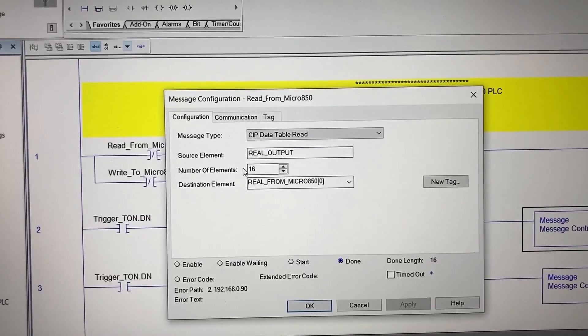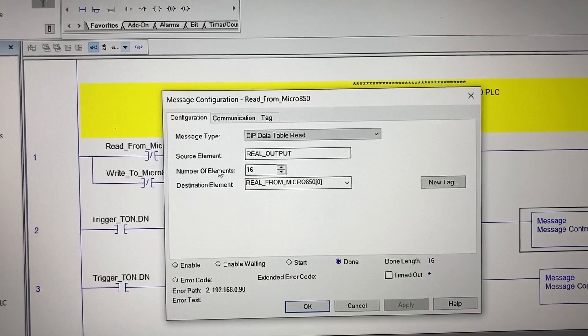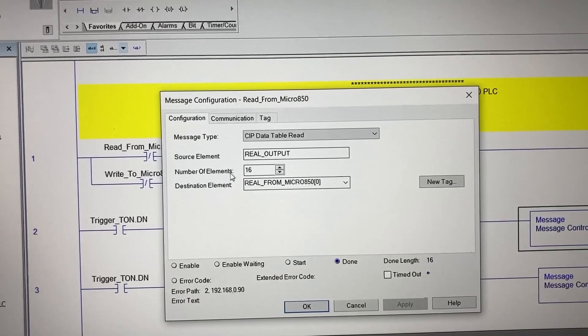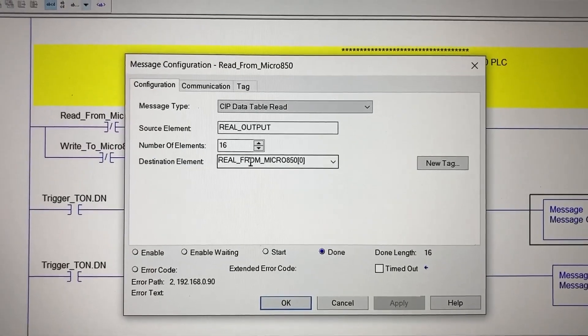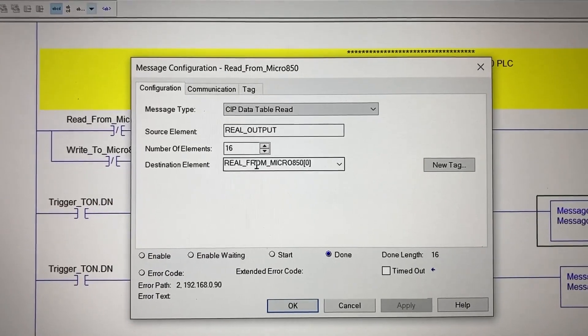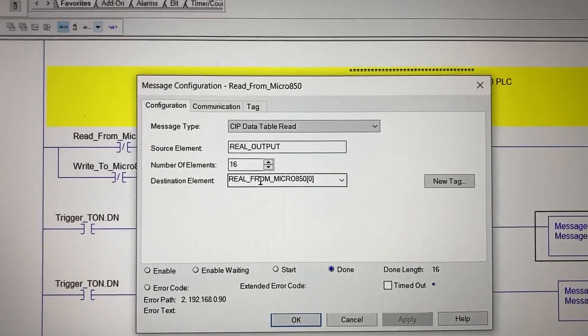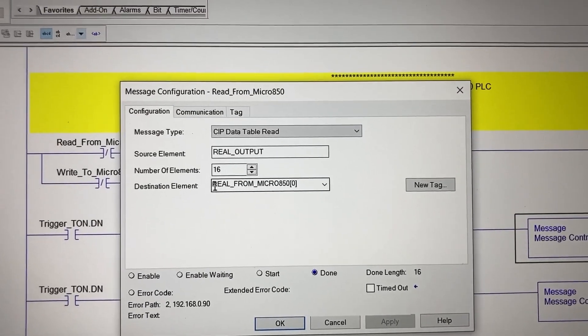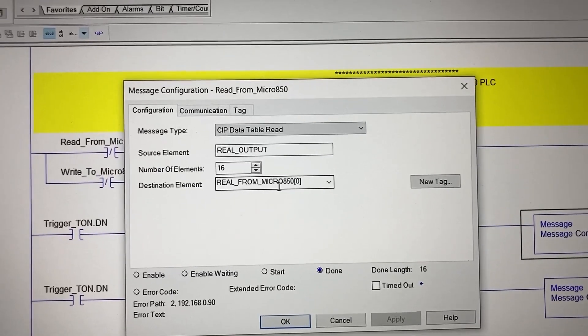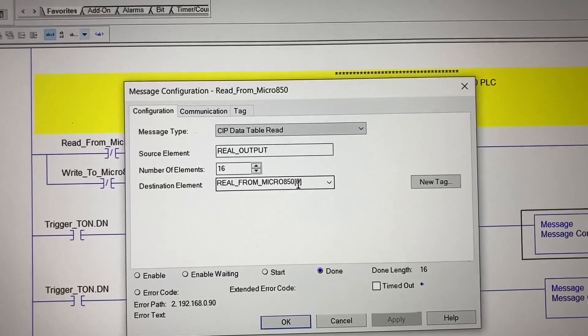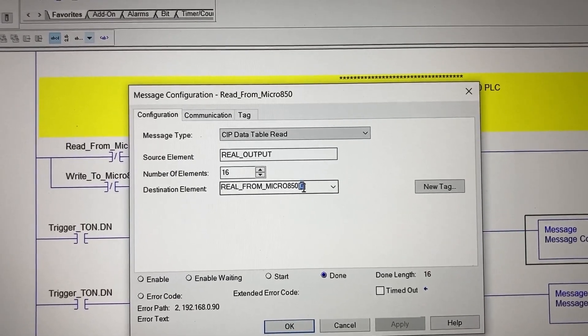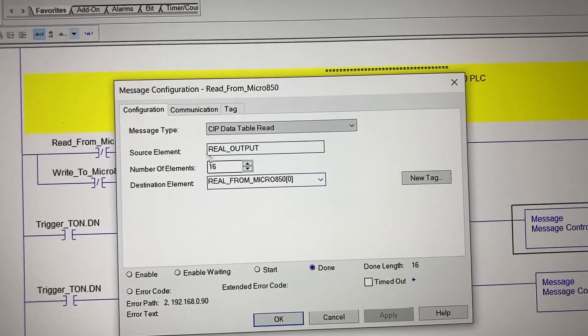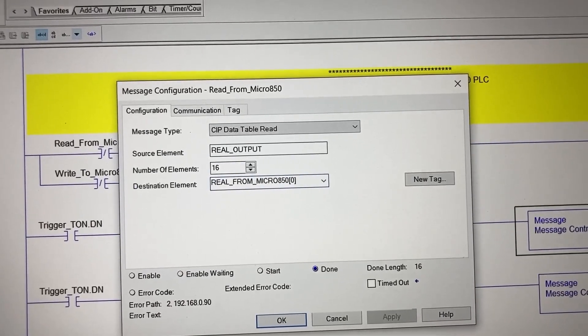Because it is an array, we have to specify the number of elements — 16. For the destination element, we have Real From Micro 850, starting from element 0, which we just created in the controller tags.